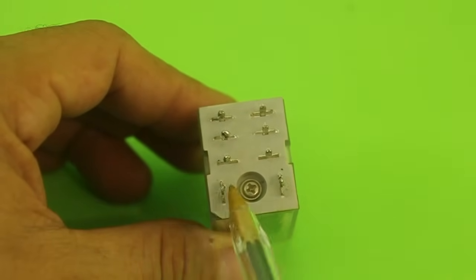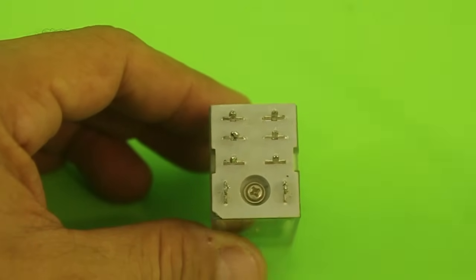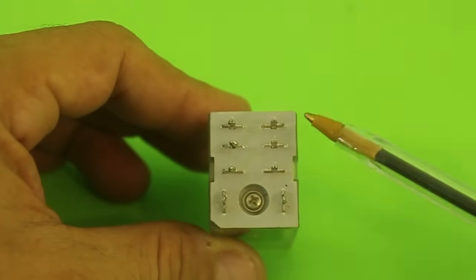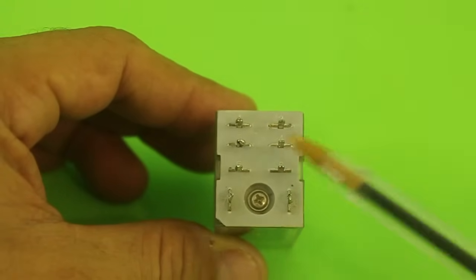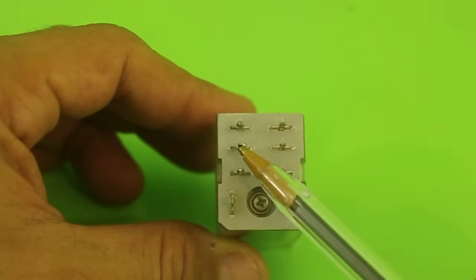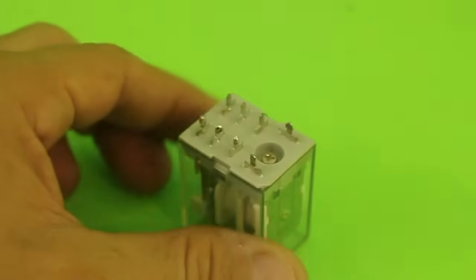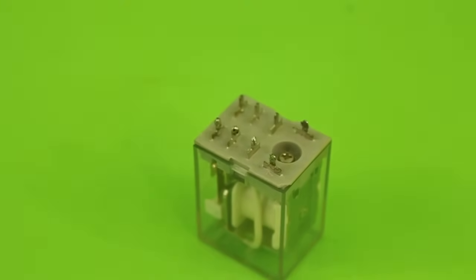Identifying the coil is easy. In this case, these are the contacts of the coil. You will measure some resistance. And here we have common, normally closed and normally open. This is one set of contacts. And we have another set, which also has a common, normally closed and normally open. It will take more time to identify all of them, but the procedure is the same.